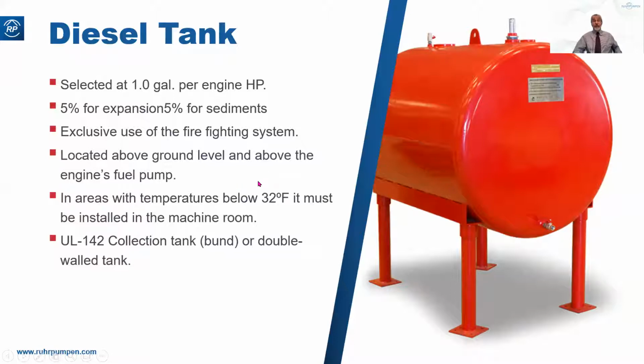You can't build it into the base plate, for example, and have it on lift. It's an interesting requirement because the engine fuel pumps are perfectly capable of operating in lift, but the specifications clearly say it must be above the center line of the engine pump. These are frequently double wall. If they're not double wall, then you have to have a catchment tank or bund underneath to catch the spillage should somebody drive a forklift truck into it or something like that.